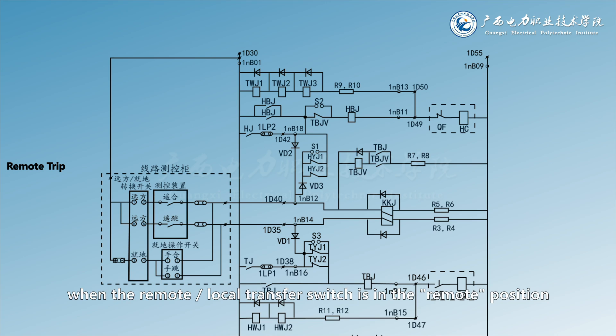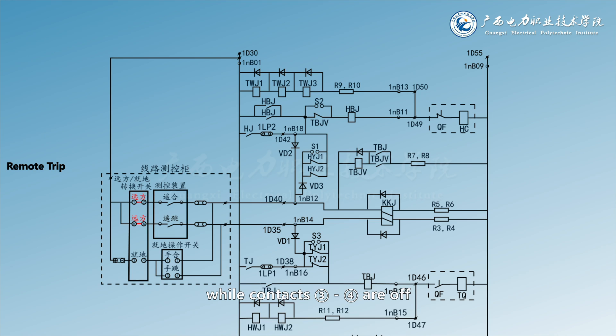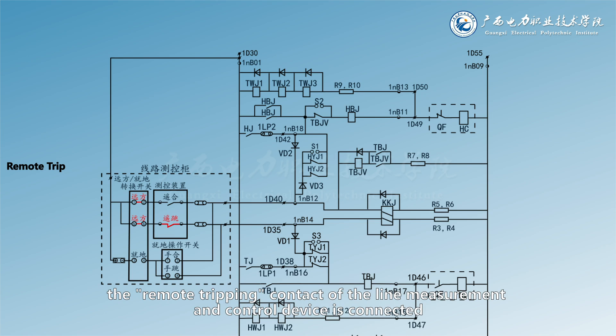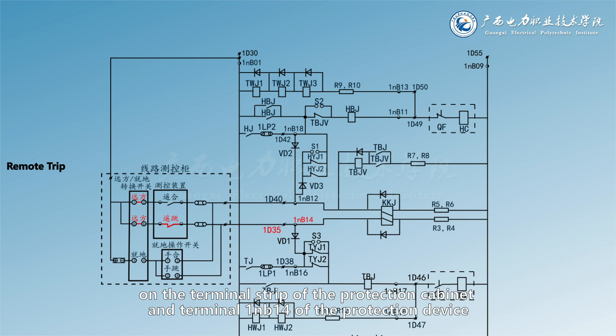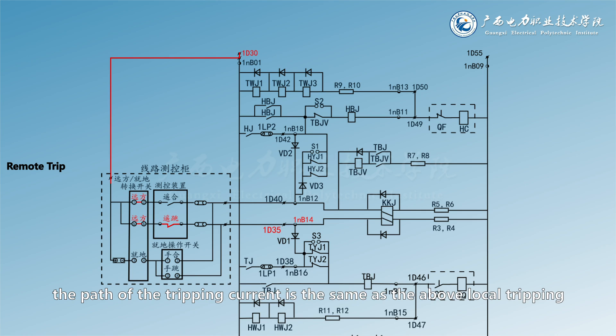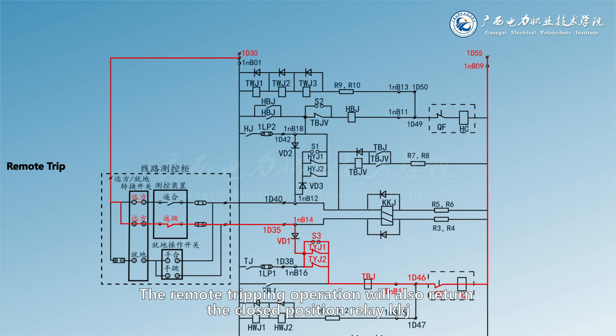For remote tripping, when the remote/local transfer switch is in the remote position, its contacts 1-2 and 5-6 are on, while contacts 3-4 are off. After receiving the tripping command, the remote tripping contact of the line measurement and control device is connected, and the positive power supply is also sent to terminal 1D35 on the terminal strip of the protection cabinet and terminal 1NB14 of the protection device. The path of the tripping current is the same as the above local tripping, so as to complete the remote tripping operation. The remote tripping operation will also return the closed position relay KKJ.